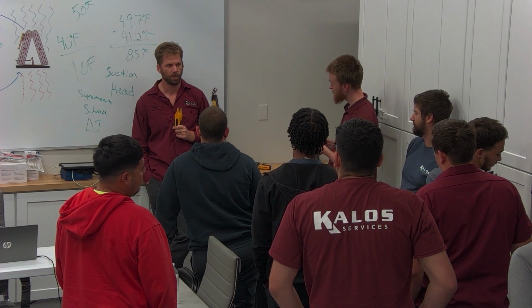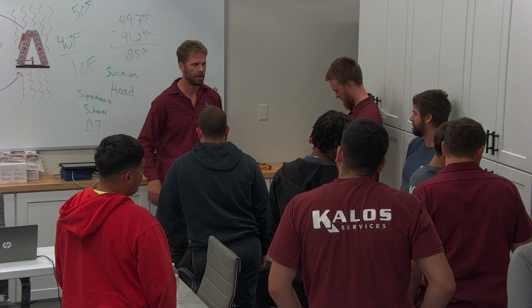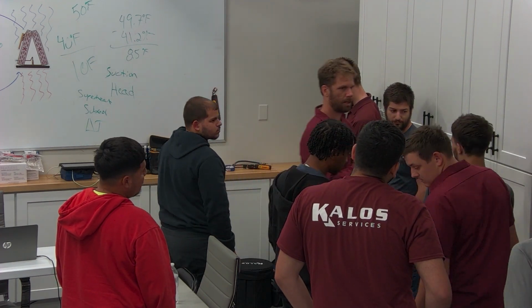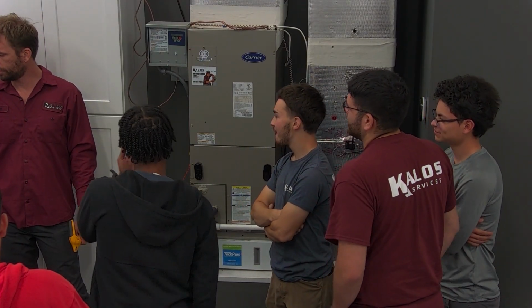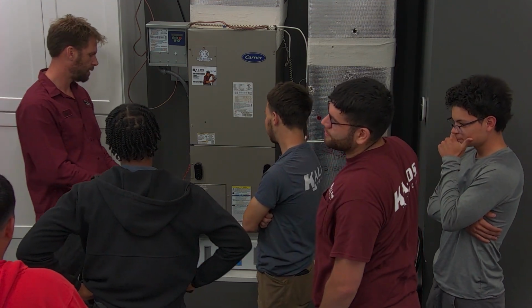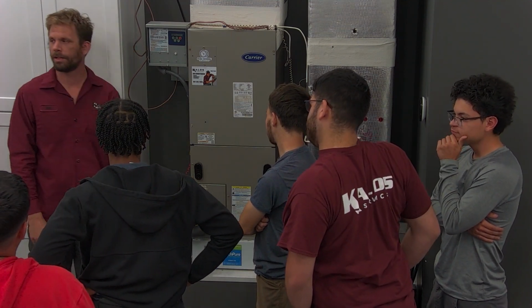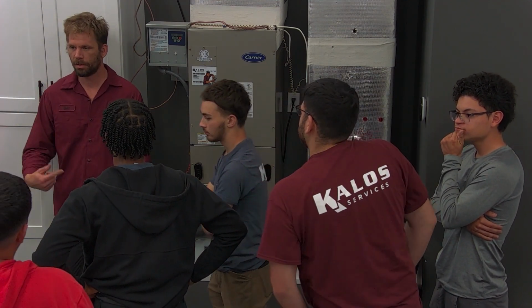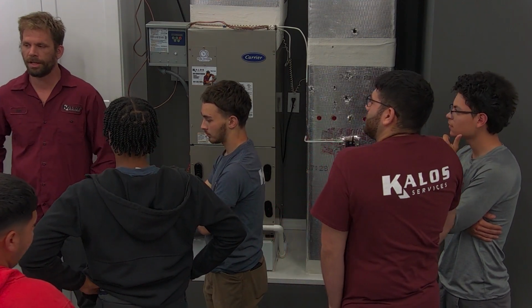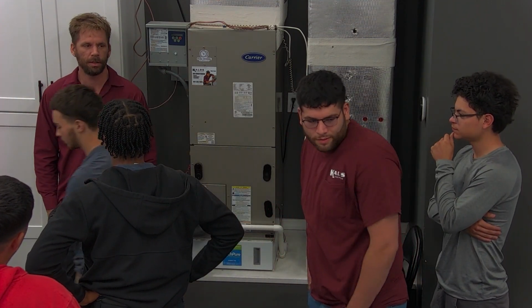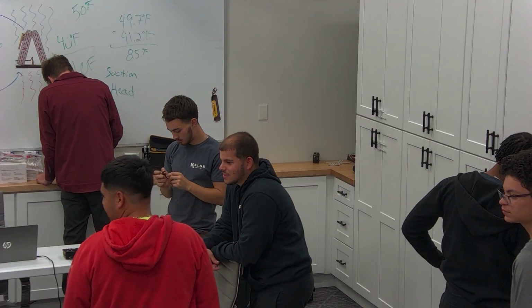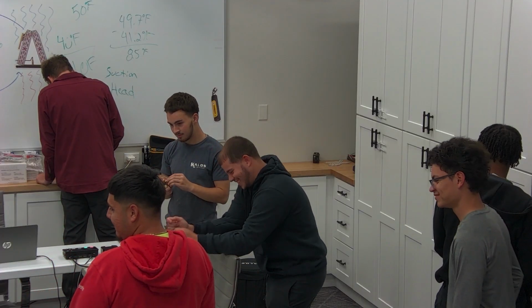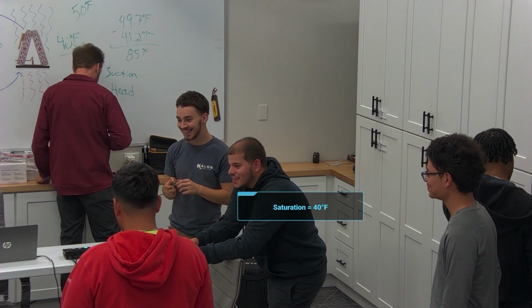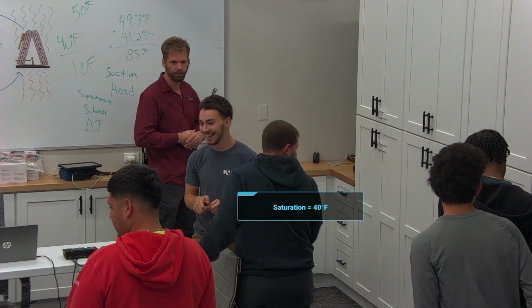Nice. Great. All right, so the next one, Alex is gonna go outside. Alex, go outside, hook up to the suction. Change your plans. Just the suction? We want superheat. So he's gonna go outside, hook up to the suction, and somebody's gonna call him on the phone and find out what we need to know in order to get our superheat. We got a saturation of 40. Saturation of 40. Right, perfect.